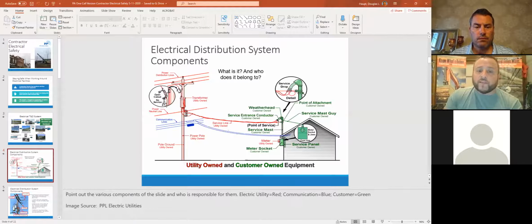We have a fuse out there. A lot of folks think we're blowing up transformers when they see that blue flash in the sky during a storm and hear a loud bang outside. Much like in your home, if something goes wrong with an electrical outlet, it trips a breaker in the panel box. Up on the pole we have what's called a cutout and a fuse, protecting the transformer just like in our homes. So that loud bang you hear is actually a fuse blowing, not the transformer itself.